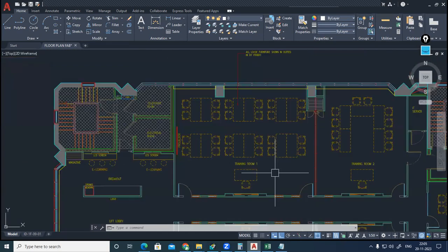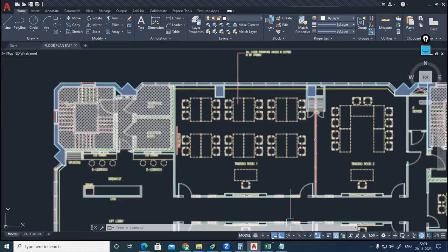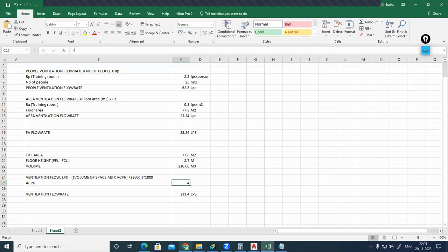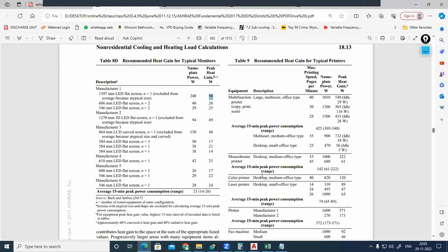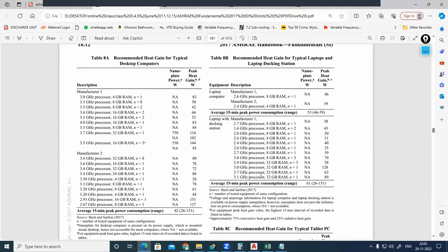See, anyhow, since it is a training room, 25 people will be there. They might be using desktop computers, though desktops have not been shown, or they might be using laptops at least at the time of training. So we should consider that 25 laptops can come inside. Then how can you give it? We have to assume it. If you are getting the nameplate from the manufacturer, then that is fine. Otherwise, you can go to here. For example, with respect to the recommended heat gain of a typical laptop, a docking station means multiple monitors, they will be docking.